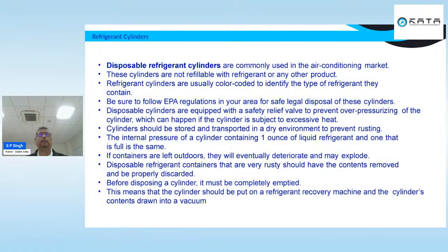We have to have regulators before we charge, we should have safety valves, and we have to keep old cylinders separately. Whenever we are charging the cylinder, we should identify R22 cylinders differently, R32 cylinders differently, and R410 differently.